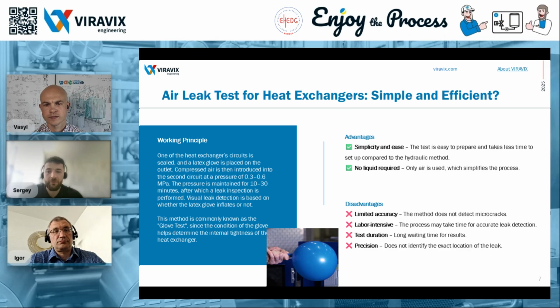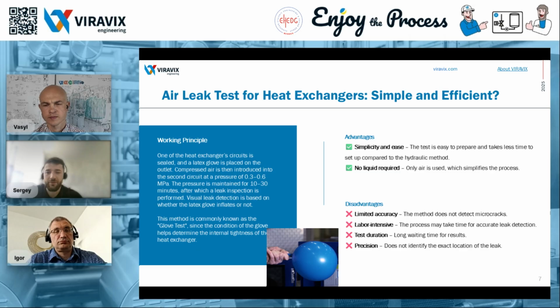Visual inspection is carried out by observing whether the latex glove inflates, indicating the presence of air leakage. In other words, it checks for internal leaks within the heat exchanger if any exist. Commonly, this method is referred to as the glove test, because a simple latex glove placed on the circuit clearly shows whether it inflates or not, indicating the presence of a potential leak. The key advantage of this method lies in its simplicity, accessibility, and ease of implementation without requiring specialized equipment. That is, it requires minimal preparation and takes even less time compared to the hydraulic method.